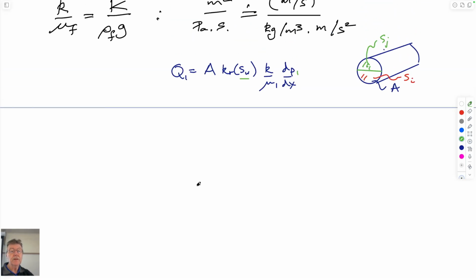And that's about it. As we said before, the end result of this is that we want to calculate heat rate. It's equal to mass flow rate of the fluid times how much heat we pick up. This mass flow rate is equal to volumetric flow rate multiplied by the density of that fluid.